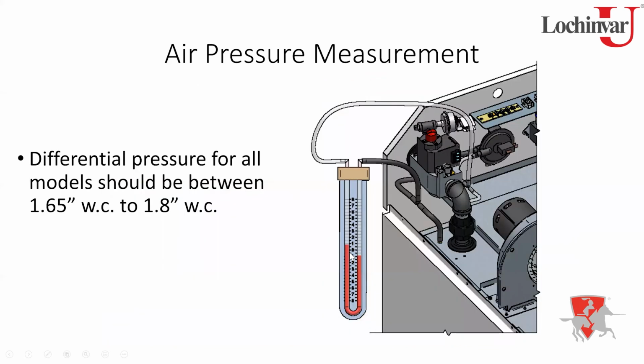So when we look at that, basically I'm looking for a differential here. So if I was to measure this, I'm measuring the difference between the deck pressure versus what's going down to that burner. So remember the burner with the little barb on it? Okay, that's measuring the combustion chamber pressure. That basically is what we're looking at there. So I'm looking at the difference between those 2 points.